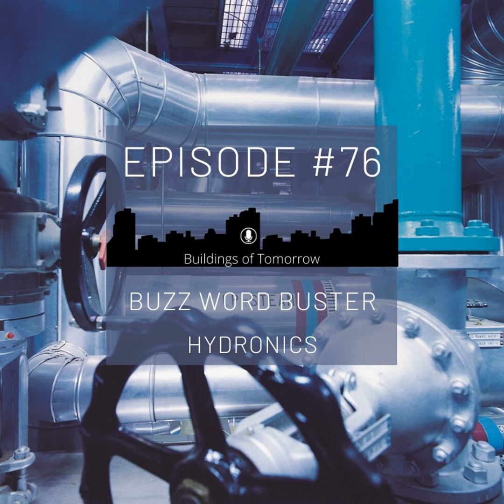Perfect. Thank you. You mentioned just then variable flow, and I think that's a really good time for us to take a step back from the valves as they are, the individual components there, and look a little bit more at the system. So what is variable volumetric flow? Okay. So variable volumetric flow, I think in today's situations is key, because when we set up hydronic circuits from the producer across the distribution all the way out to the consumer, we really want to have variable volumetric flow, meaning we only want to move as much water as it is currently needed through our system with the pumps.